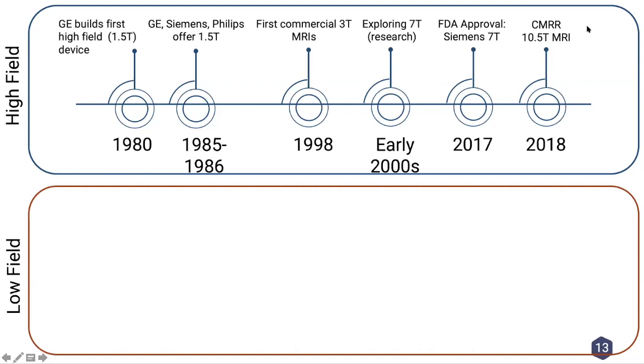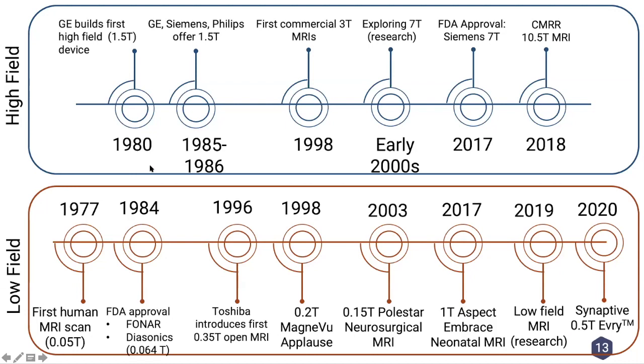At the same time, in parallel, low-field MRI never went away, it's been here the whole time. The very first human scans back in 1977 were on a low-field scanner, a 50 millitesla scanner. Diasonics, Toshiba, and Fonar have been using 64 millitesla, or 0.064 Tesla, since 1984. That's the field strength used on the Hyperfine scanner, and also the field strength used at the Martinos Center for some of the systems made there. So it's a viable field strength, known to be viable since the 80s. It's just that high field users followed their own path, and low field users were doing their own thing.